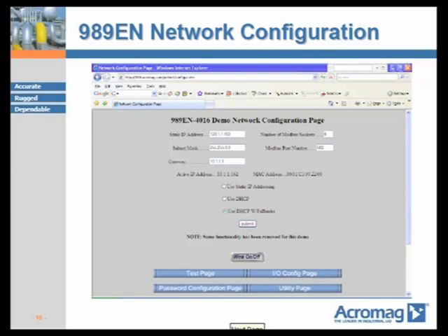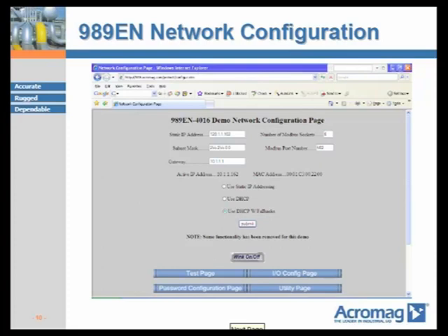The 989EN has an easy-to-use built-in web page for browser configuration. Reviewing the network configuration page, you'll notice the 989EN can be used for static IP addressing, dynamic DHCP addressing, or dynamic addressing with fallback to static IP if DHCP fails. In the upper right-hand corner, each 989EN can support up to five Modbus sockets or sessions at one time — a programmable number between one and five — meaning up to five masters can talk with the device simultaneously. If security is critical, this number can be reduced. The 989EN also offers programmable port numbers; port 502 is the standard Modbus TCP/IP port, but other ports can be used for security or other reasons.